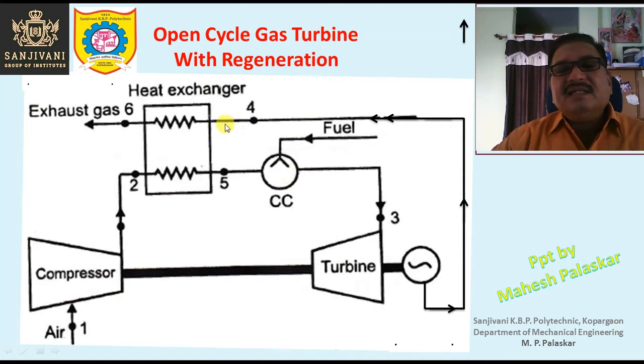So this heat which is present in the exhaust gases, which would otherwise go waste, is utilized in this regenerator or the heat exchanger. So this is a special heat exchanger, and that is the regenerator. In this regenerator the heat is utilized, and due to the proper utilization of the heat energy, you will find that the heat supplied will be reduced, and thus the efficiency of the gas turbine is improved.